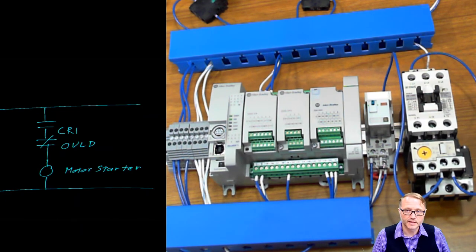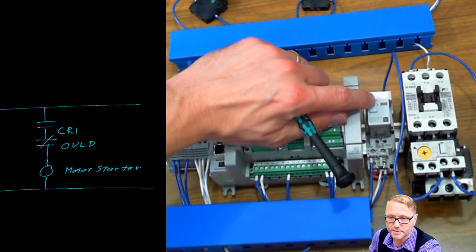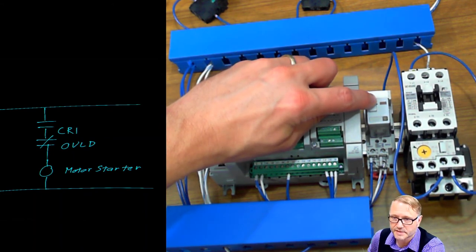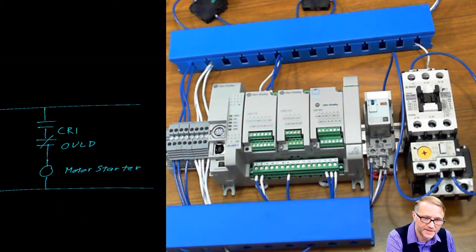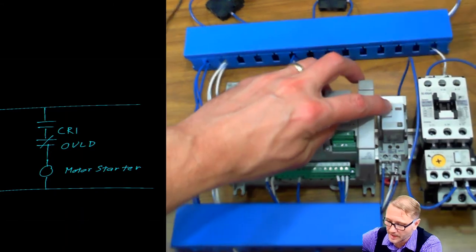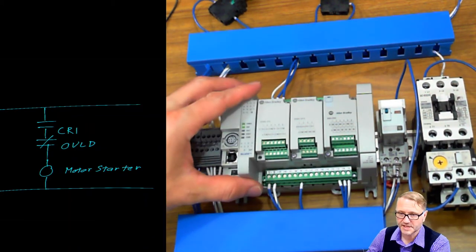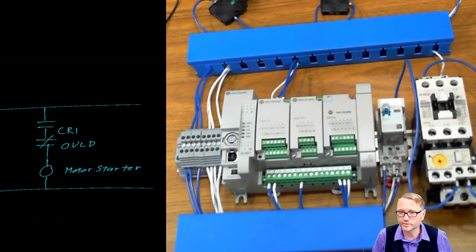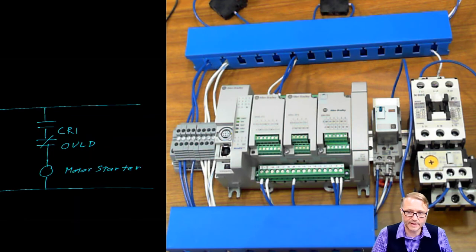I did mention something about forcing a relay. Let's do that and see what it looks like. So what we're going to do is we're going to go over here to this interposing relay and we're going to push this button. Do you see what happened? When I push the button here this relay activates. Or another way of saying that is when I activate this not electrically now mind you but by forcing the relay we establish electrical contact here and this line evaluates as true. So we push it and you'll notice you can maybe see the orange there but there's no green light. Okay so that's forcing a relay. This particular relay actually has a feature that allows you to do that permanently. So you can push this tab open and it'll hold the relay mechanically activated. All right so far so good. Let's go back and talk about this motor starter.